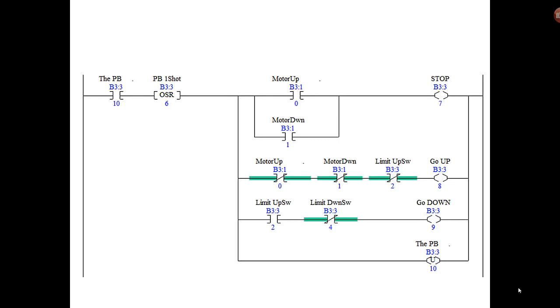Meaning that this instruction executes on the rising edge of whatever is to the left. So when everything to the left of the OSR is true, then the rung, that far it goes from false to true—that's the rising edge, false to true.